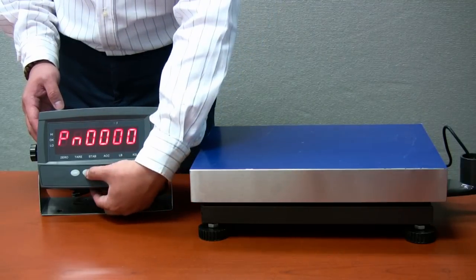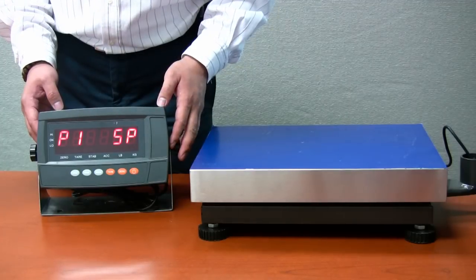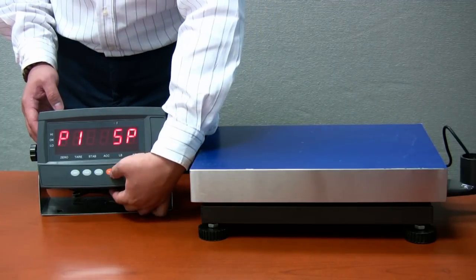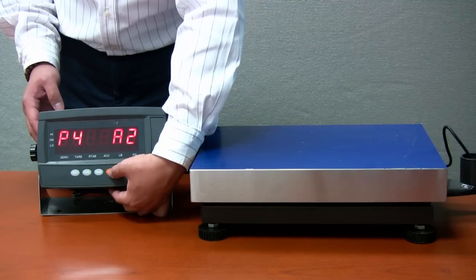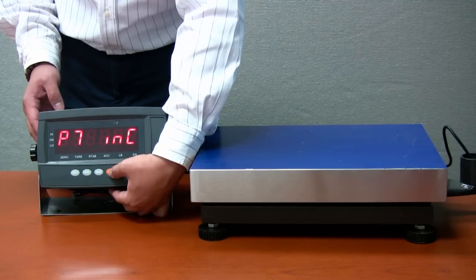Press function key and the indicator will show P1. Press TARE seven times and the indicator will show P8 C-A-L.